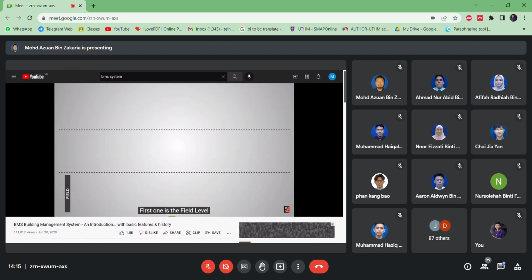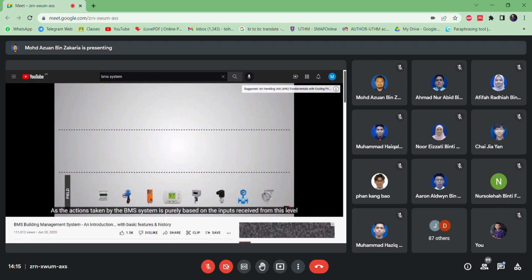The first one is the field level. This level refers to sensors, instruments, valves, actuators, thermostats, IO modules, etc. This level plays an important role in the building management system, as the action taken by the BMS system is purely based on the inputs received from this level.